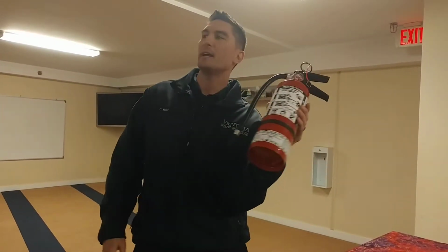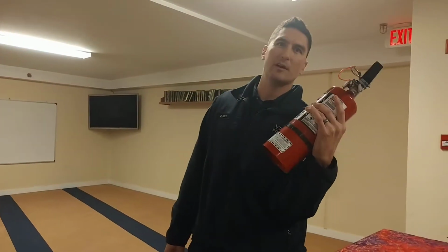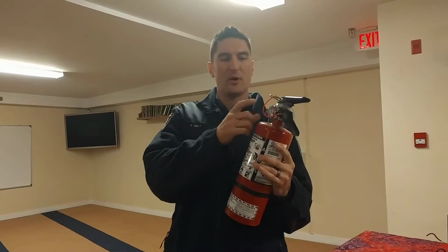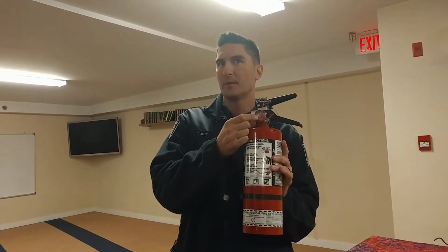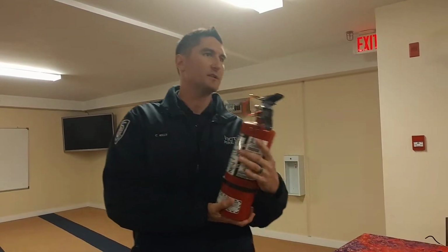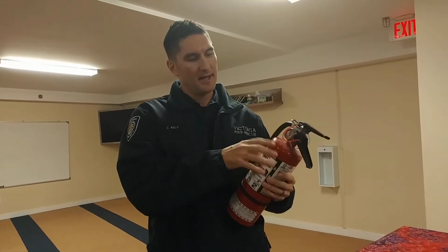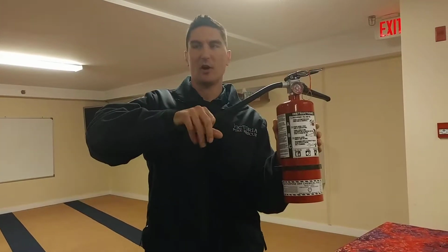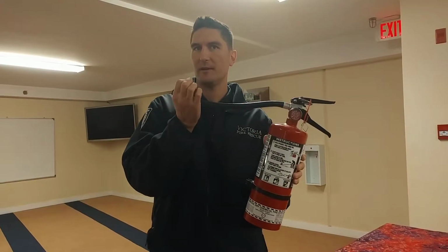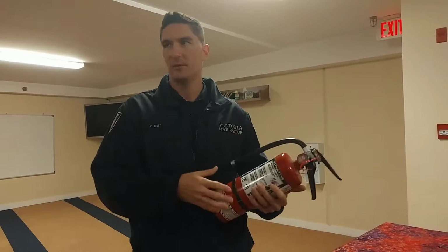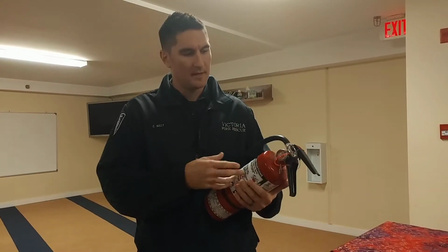And these ones, like I said, you'll see them everywhere. Sometimes they'll be white, sometimes they'll be orange, depending on how old they are. But the majority of the time, they're red. They look just like this. They always have a pressure gauge on them. So if you went to a building and saw a big red extinguisher and it didn't have a pressure gauge and it had a hard horn object on the end of it, that would indicate that it's a carbon dioxide extinguisher, and that would only be good for electrical circuits.